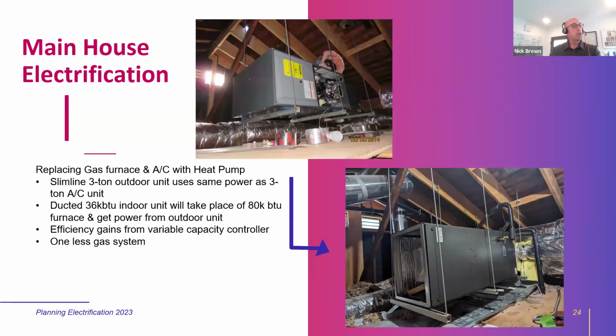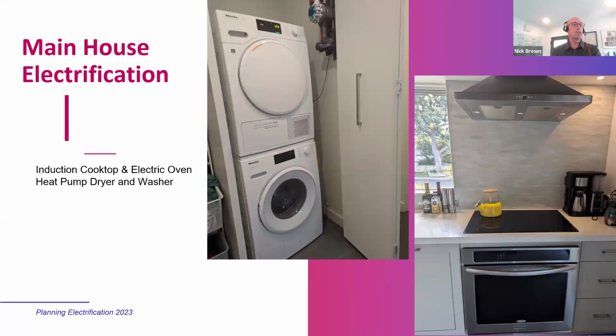And it's worked just great. We electrified the gas furnace next with what's called a multi-position air handler from Mitsubishi. You see, it's the same rough size. We took out that air handler furnace combination and hoisted up this heat pump, changed out the outdoor unit as well, and used the same power circuit that the air conditioner alone used. It actually frees up the circuit that your air handler was using when you switch to a heat pump like this, and they work much more efficiently thanks to being inverter driven and variable speed.